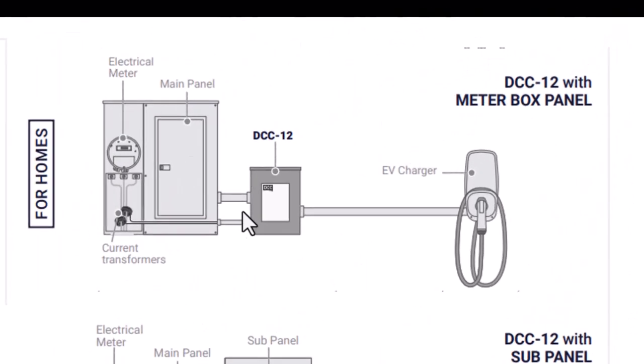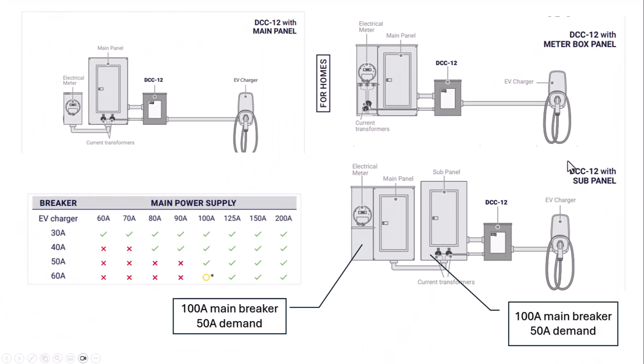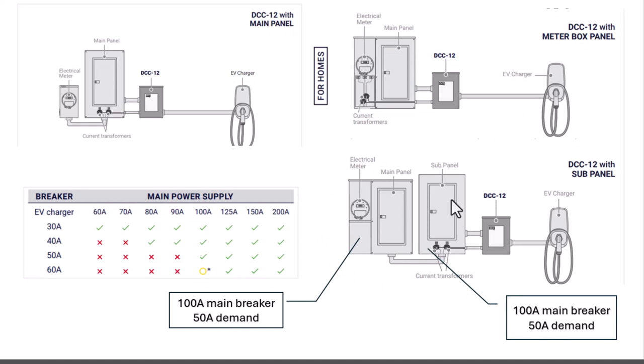And you basically place it such as this. These are just two examples of how to install this box. You can have a breaker that feeds into this, and then it goes through this to your EV charger. You can also have some sort of configuration like this where it is off a sub panel that is coming off the main. And in this case, you have to be a little bit careful, and when you calculate the main demand to your meter with the EV charger, you still want to make sure that it falls underneath the main overcurrent protection device. So what this means is, let's say your demand is more like 50 amps for this, even though the main is at 100 amps.